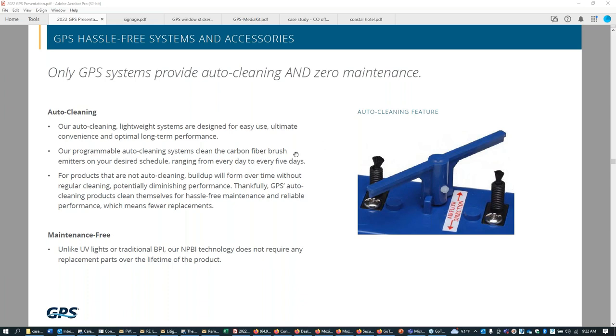What's really nice about this, and when we talk to maintenance people and property managers, they really like the fact that this technology can be installed, commissioned, and then there's no ongoing maintenance, there's no replacement parts. We feel like if this product is installed correctly, it'll last at least 10 years. We recommend not cycling it since there's no ozone being generated. We recommend that it just be allowed to run. And then when the air comes on, the airflow rolls over the device and delivers ions into either the coil or into the airspace.